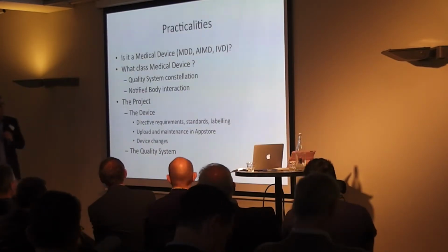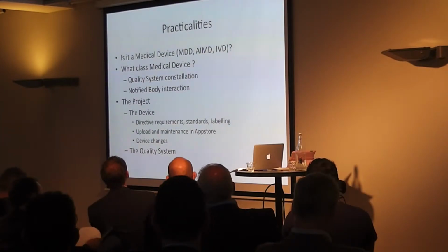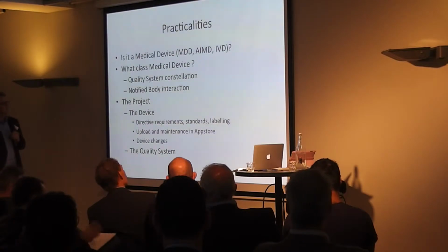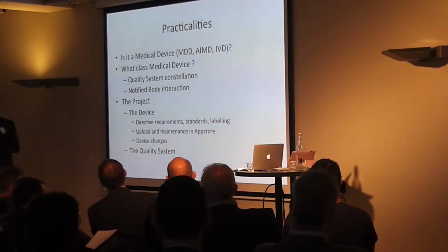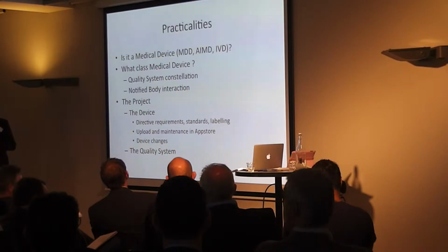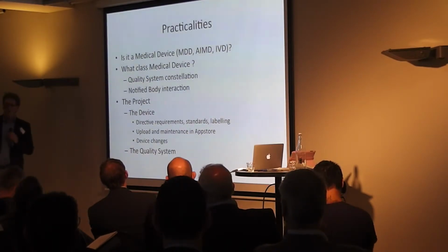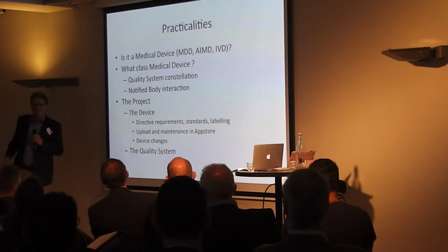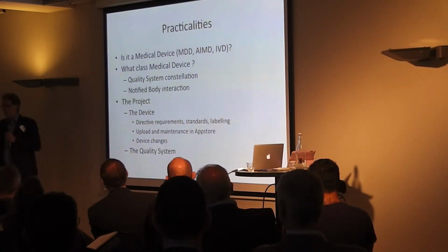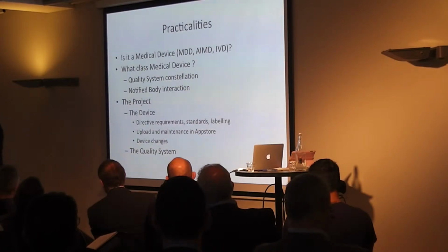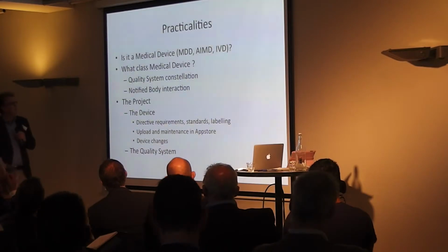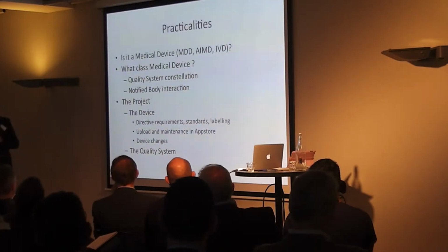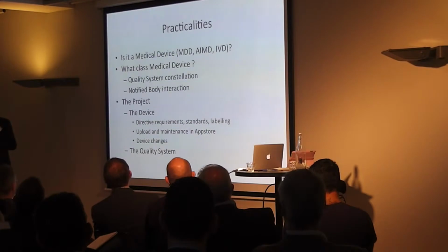So what will be discussed? Is it a medical device, and if so, under which directive will it fall? Is it an MDD product, is it an active implant, or is it an IVD? Products can be active implants. For instance, if you have an implant or neurostimulator and a patient programmer to program the mode of that product, and you bring that onto an app, your app will be classified as an active implant medical device with specific requirements. If it is a medical device, what class is it?